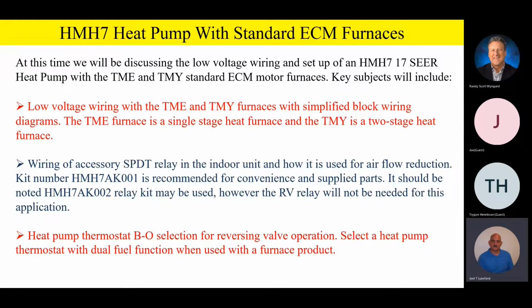So the outdoor unit, our outdoor unit, and our indoor product, we don't have dual fuel kits built into them. And so we're depending on the heat pump thermostat to switch over from heat pump to furnace and so on. So be sure that you select a heat pump thermostat with dual fuel function. And you'll find that most of your better heat pump thermostats have that dual fuel function anyway. They may require an outdoor sensor. They might be Wi-Fi driven, to where they know the outdoor temperature by the Wi-Fi.